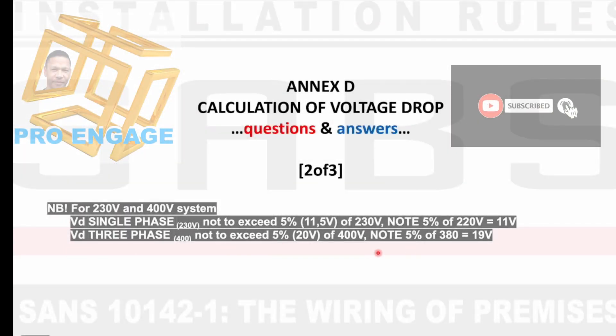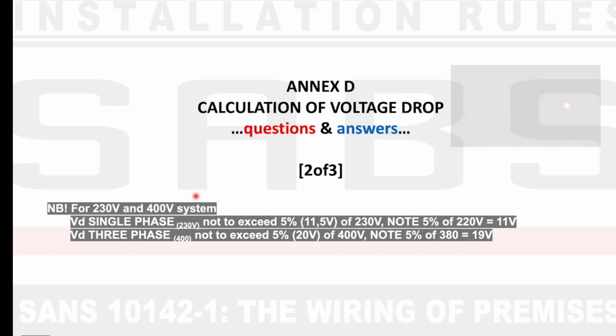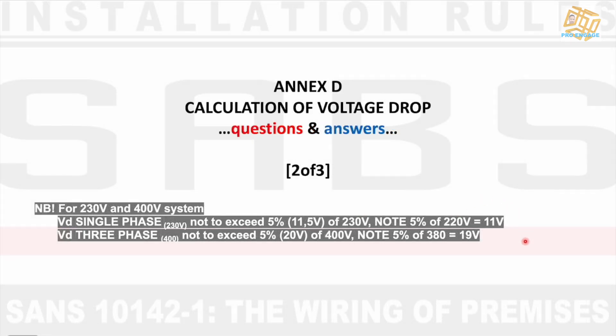We have the same information as before, which will come in handy as we carry on. We're working with two AC systems: 230 volts single phase and 400 volts three phase. The maximum allowable voltage drop must not exceed 5% for either single phase or three phase. Single phase can be 220 V or 230 V, and three phase can be 400 V or 380 V. If the voltage is not given, we use 400 V for three phase and 230 V for single phase. Bear in mind that the percentages will differ slightly.